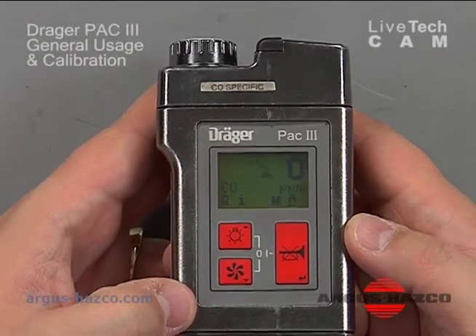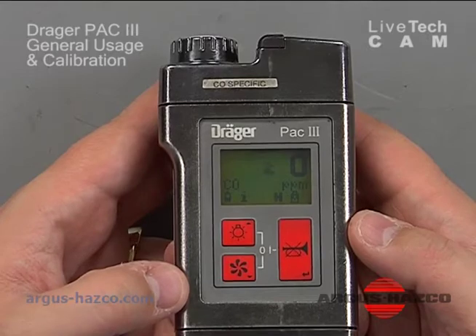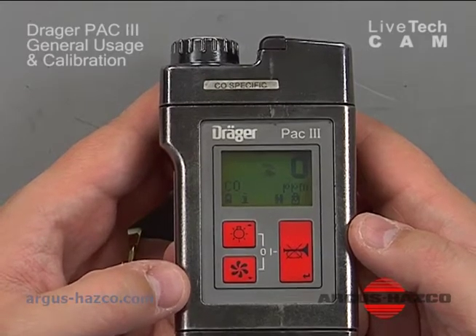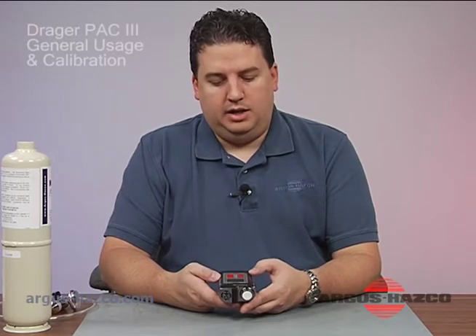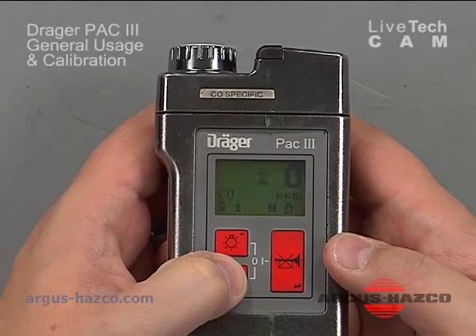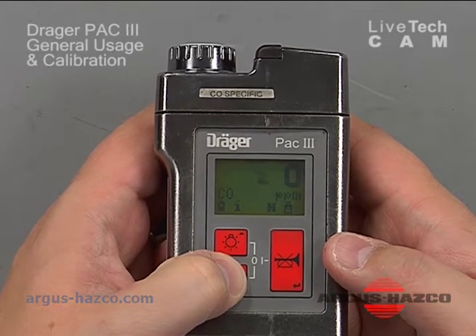You can program those to do your 0 calibration, which is done frequently every day, before each use. And also you can use it to set up for your span calibration. A hotkey is just you pressing 1 key to get into that mode without having to go through the other mode to get into calibrate. So if I press and hold this down arrow, it has a hotkey set up to be able to 0 the sensor. So you have to keep holding it.